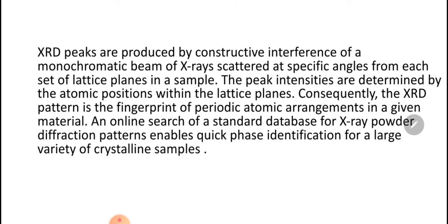X-ray diffraction peaks are produced by constructive interference of a monochromatic beam of X-rays. X-rays are monochromatic, scattered at specific angles from each set of lattice planes in a sample. The peak intensities are determined by the atomic positions within the lattice planes. Consequently, the X-ray diffraction pattern is a fingerprint of periodic atomic arrangement in a given material. An online search of a standard database for X-ray powder diffraction patterns enables quick phase identification for a large variety of crystalline samples.